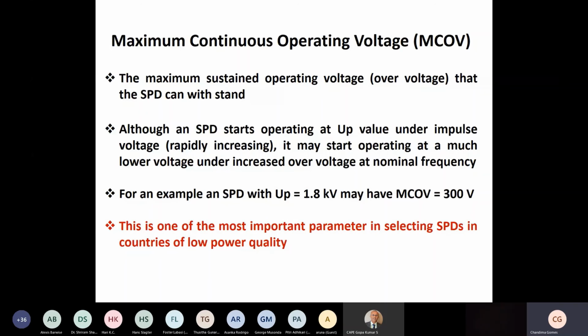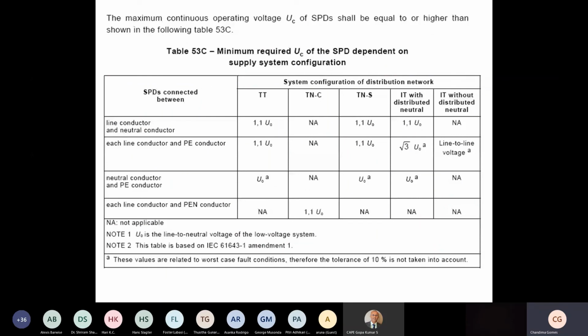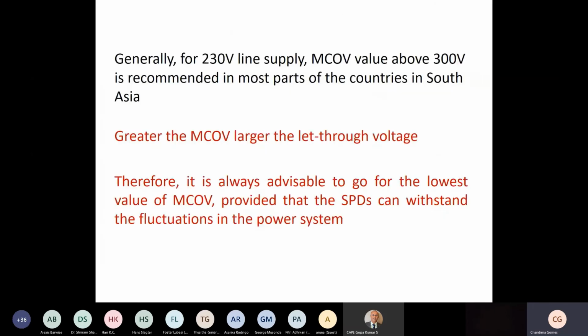What IEC says is that for a TT wiring system, for example, the MCOV should be at least 1.1 U0. That means 110% of the nominal RMS voltage. But what we have seen in many countries where the power quality is bad, such values, for example for 230 volts, then it's about 255 volts, the MCOV according to IEC standards.